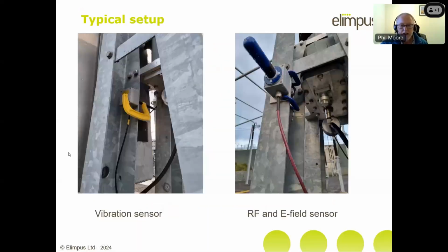There are two photographs just showing how the sensors are attached. So this is the vibration sensor. This is the bottom of the mechanism in this particular circuit breaker, so we normally try to put it close to the mechanism. In reality, it really doesn't make too much difference where you put it. When a breaker operates, the whole frame shakes quite a lot, so you could put it pretty much everywhere. What you do have to do is put it in the same position on all the phases, though.